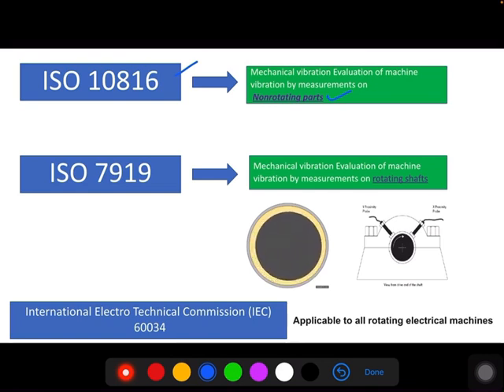Apart from 10816, there are some other standards also being used by industry. For example, ISO 7919 is a vibration standard mainly used for the evaluation of machine vibration by measurements done on rotating shafts. In case of 10816 it was non-rotating parts, but here it is on rotating shafts. It is mainly used for the journal bearings of turbo machinery or generators. Here we generally use non-contact transducers, maybe eddy current probes, and they are mounted at 90 degrees apart.